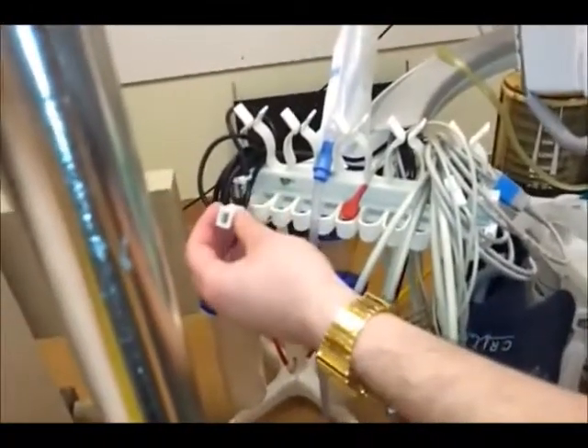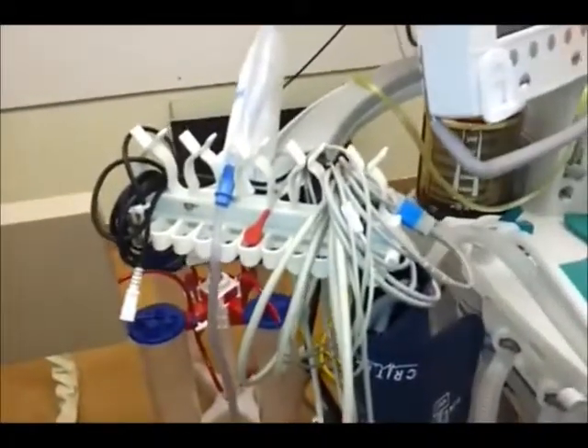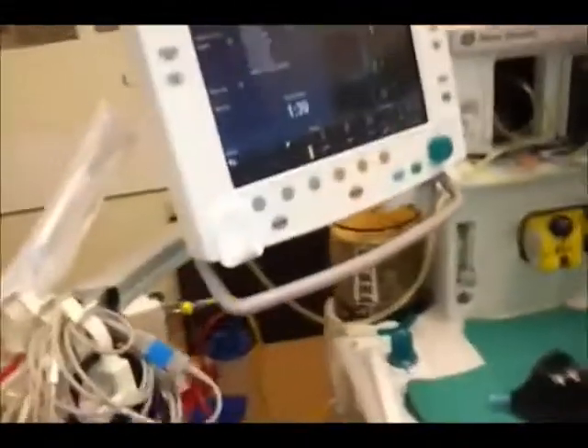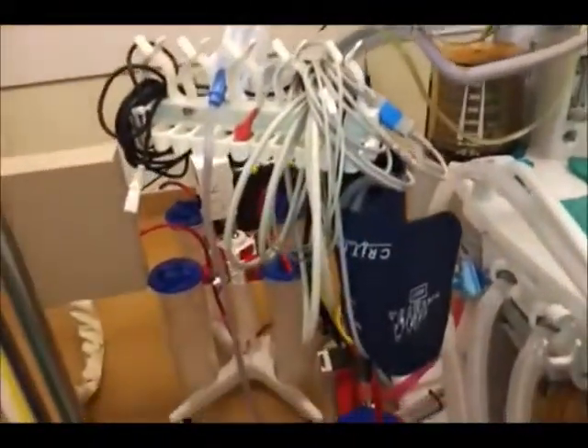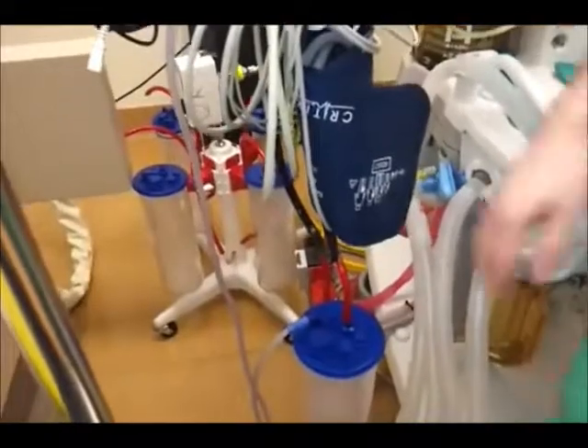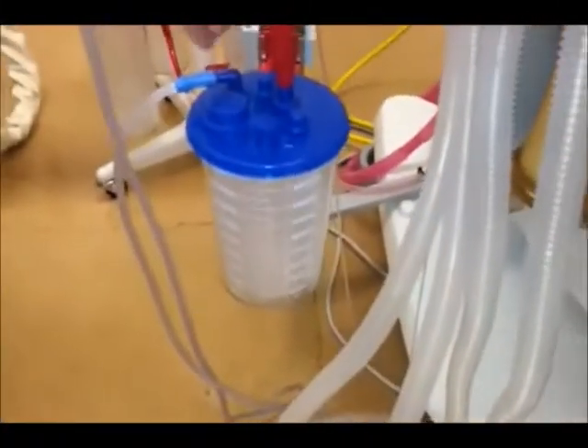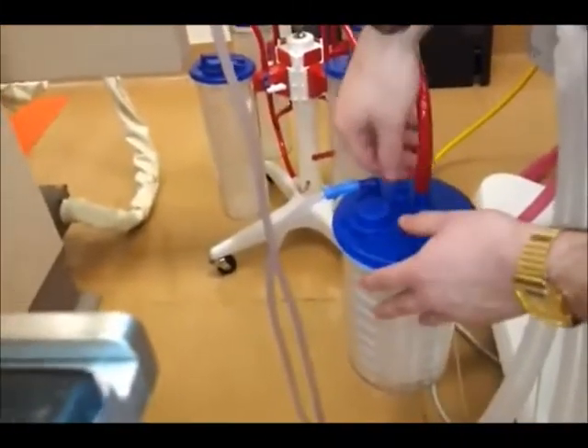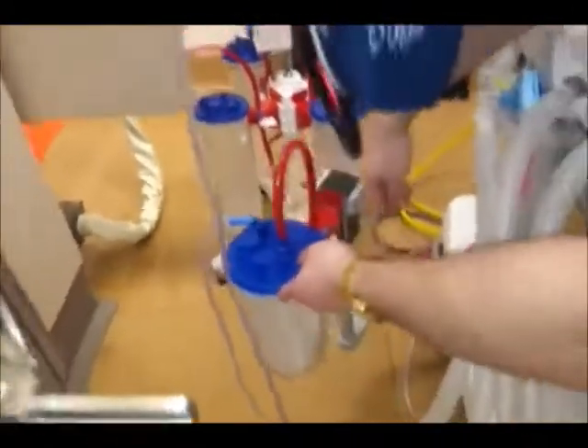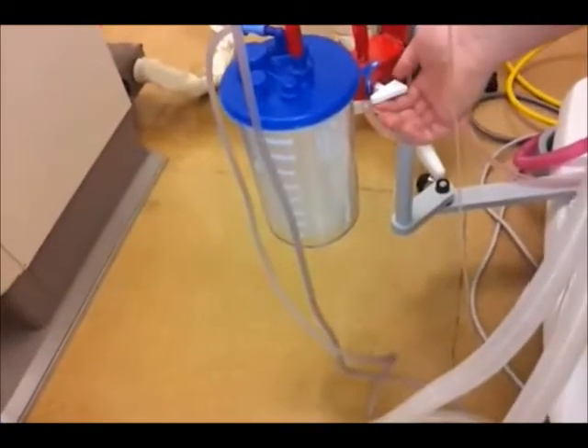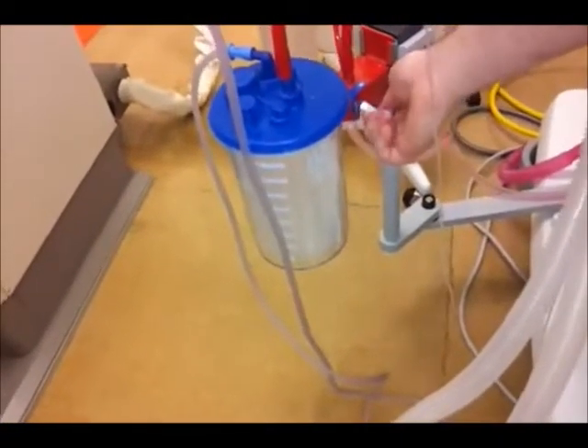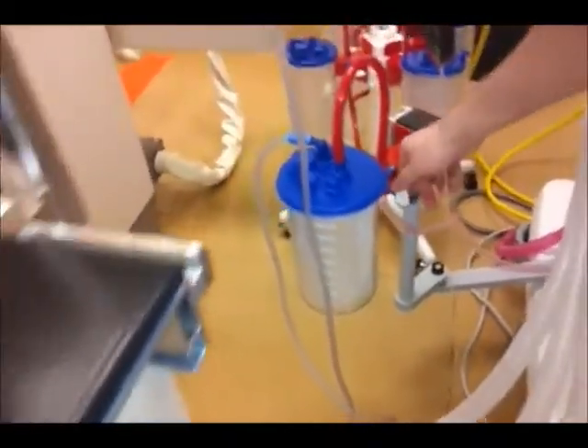And then this is the temperature probe. It has little adapters here to put on it. Some anesthetists use it, some don't. So if you need to use it, that's where that is. And your suction canister is down here. You want to make sure that everything's connected nice and tight so it doesn't come off when they're trying to use it. And another thing is, if it's not working, you want to make sure that this here is not in the off position, because then you won't get any suction. You always want to make sure it's in the on position.